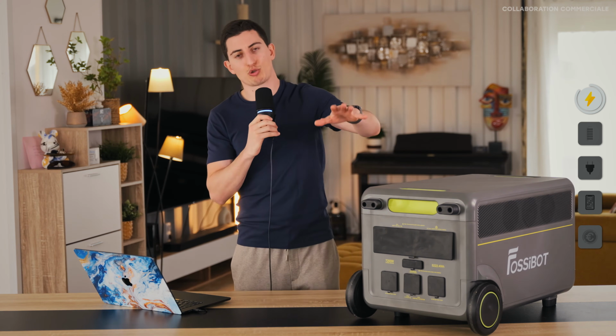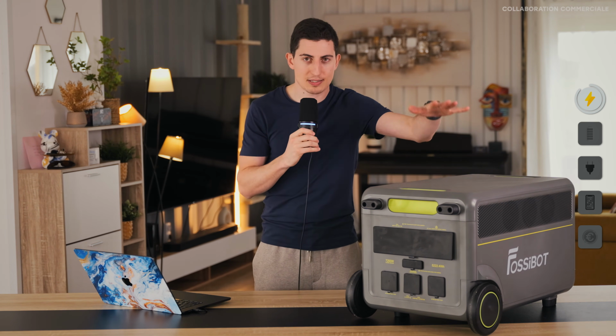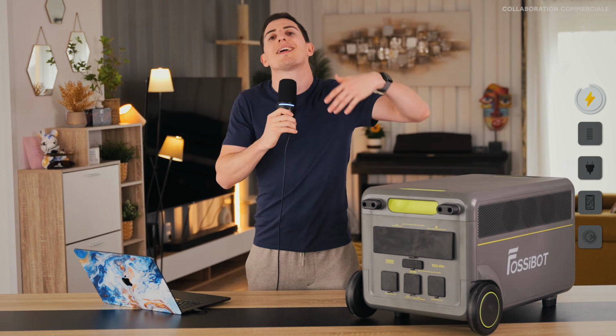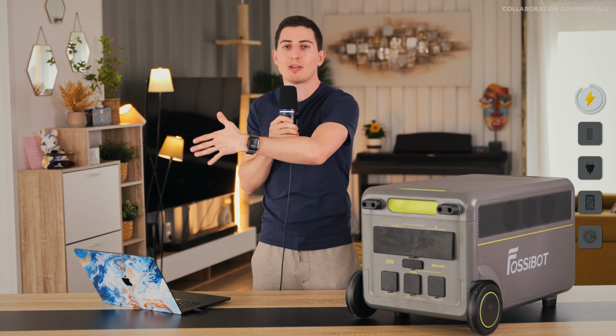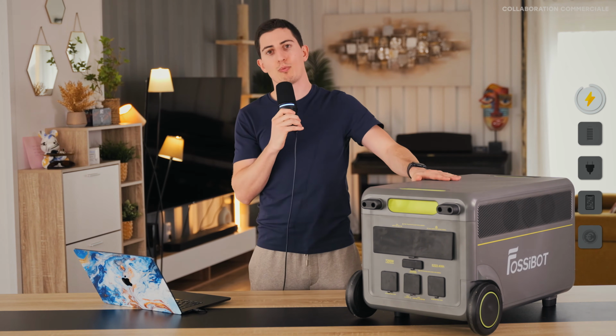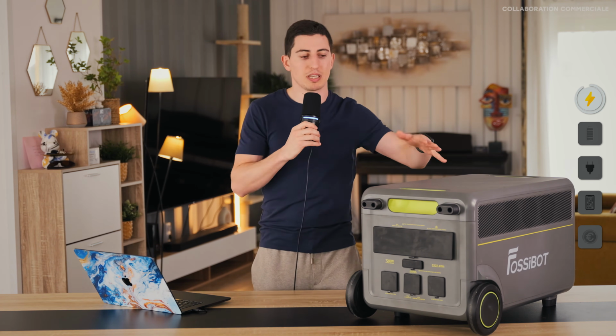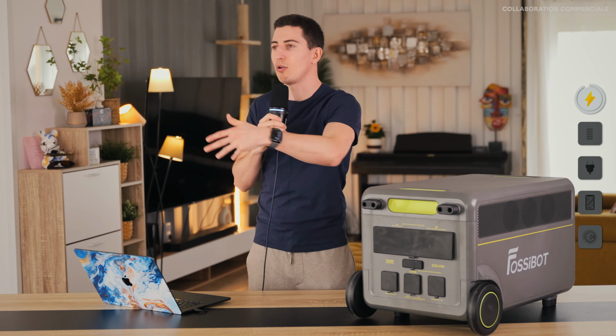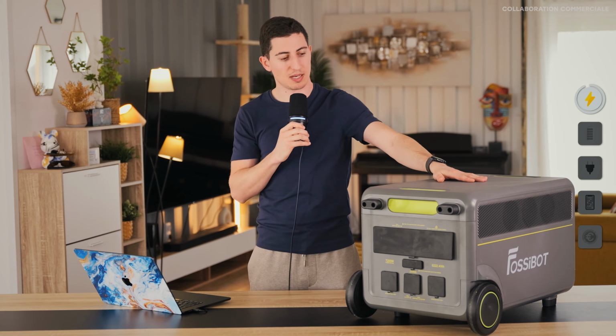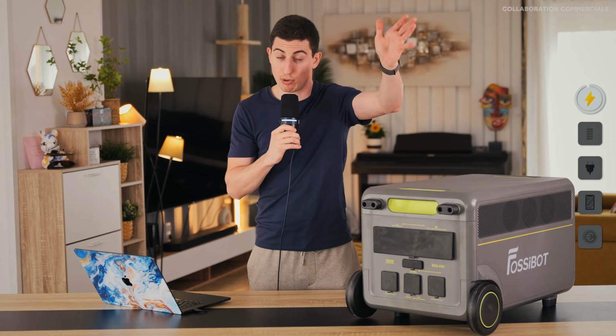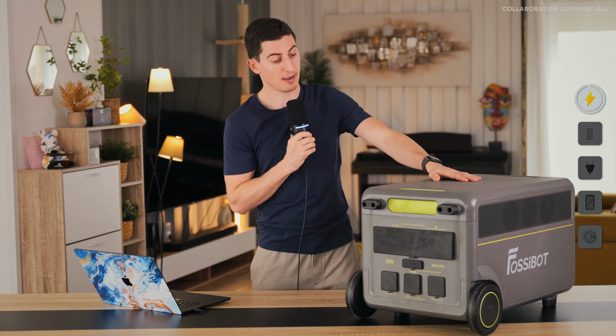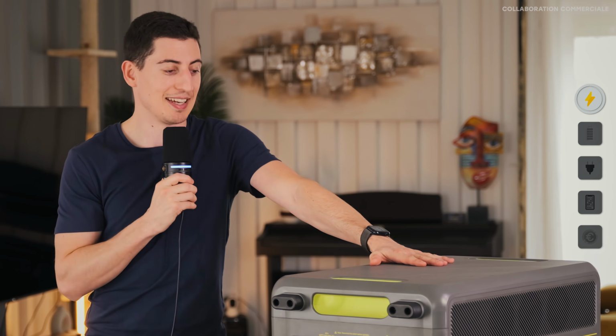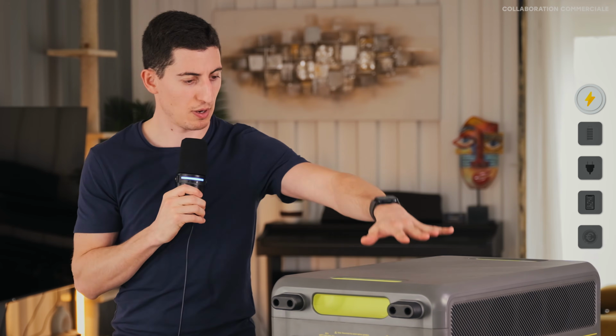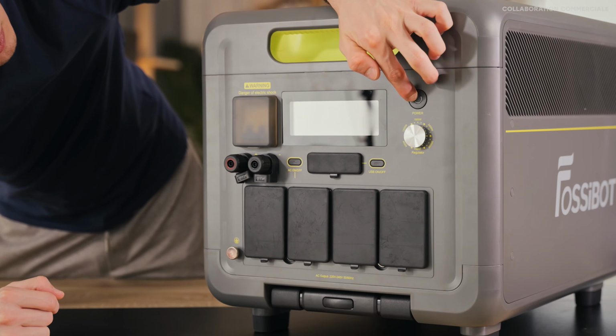So here's what I advise you: you can connect 3,000 watts of solar panels to this battery without any problem, and at worst, the extra 700 watts. Install panels that can be easily removed so that, from an insurance point of view, you have 3,000 watts in fixed panels and 700 in foldable or easily movable ones, which won't count, and you can remove them at the last minute if there's a problem. Anyway, that was my advice. So, 3,000 watts to stay within the law, and 3,700 if you want to push the system to its absolute limit.